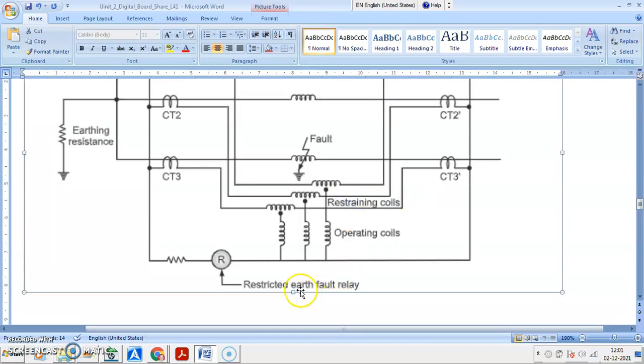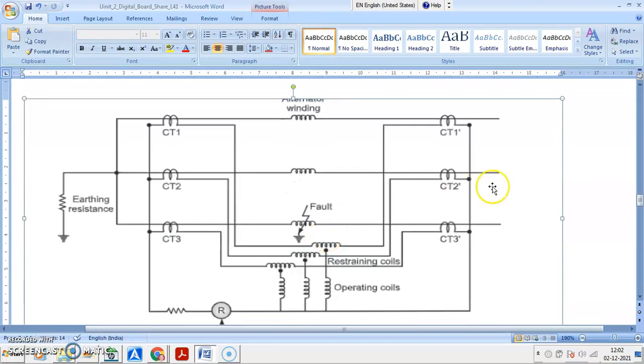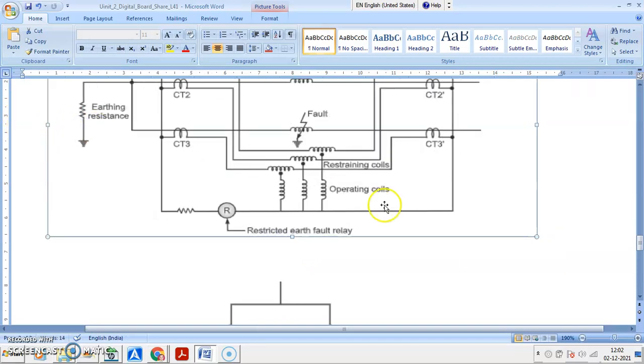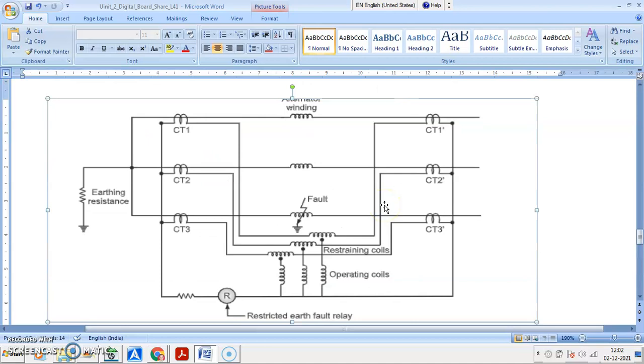Then one more protection. Now this is unrestricted; next is restricted earth fault protection in case of alternator. तुम्हाला समजतंय का रे सगळ्यांना? Restricted earth fault protection. Diagram दिसते सगळ्यांना? Now this is a restricted earth fault relay connected. So here you are having the current limiting resistor connected in the earthing circuit. Alternator, this side is star connected. Neutral is grounded through current limiting resistor. Alternator stator winding RYB connected to busbar. CTs are connected on either side of the alternator stator winding: CT1, CT1 dash, CT2, CT2 dash, CT3, CT3 dash.